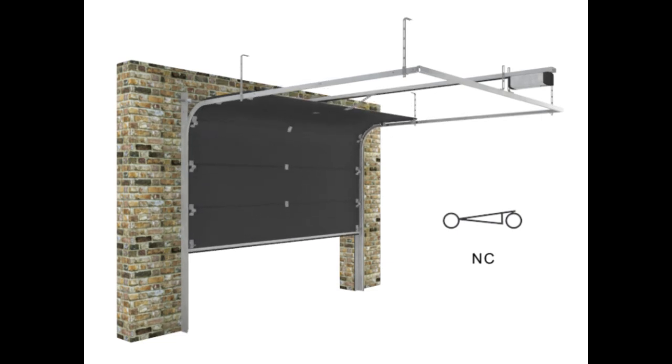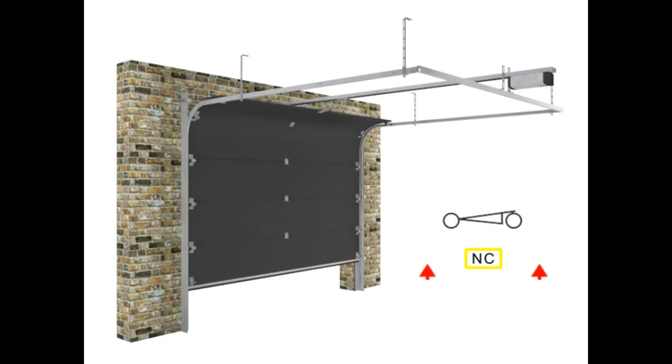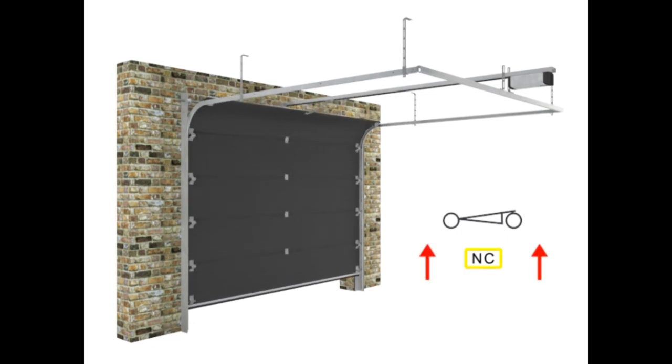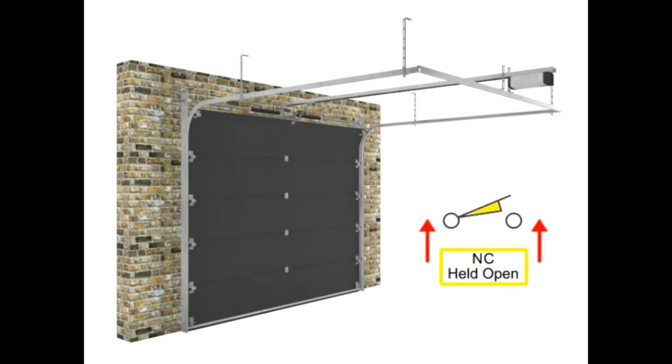When opposing pressure is applied to the normally closed LIMIT switch, current to the motor is interrupted, stopping the motor and bringing the door to rest in a down position. In this way, the LIMIT switch defines the LIMIT of movement of an object.